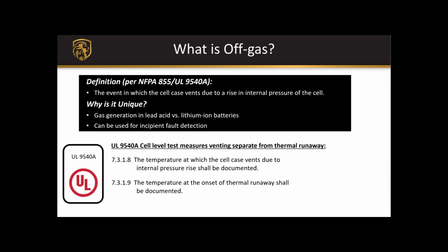We're going to ask another high level question, and that is: what is off-gas? The event of off-gas is now defined in NFPA 855. It's defined as the event in which the cell case vents due to an internal rise in pressure of the cell. That definition comes from the UL 9540A cell level test.